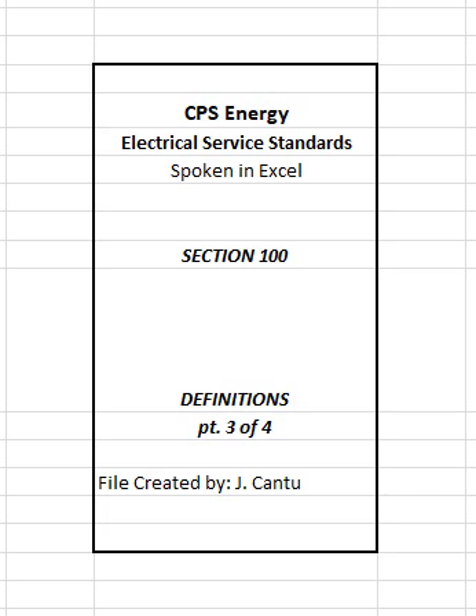The unit may be pad mount or concrete embedded on or in a minimum 18-inch diameter by 20-inch depth concrete base, refer to Figure 1501. Meter room, electrical. A dedicated room approved by CPS Energy that is provided and maintained by customer solely for housing electric meters and service equipment. The room and equipment therein shall be readily accessible to authorized CPS Energy persons. Customer shall provide permanent lighting in the meter room.